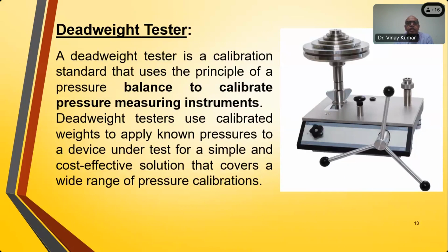The most common and accurate device is the dead weight tester. It is used as a primary standard, and it is a very simple, cost-effective solution covering a wide range of pressure measurement. In this dead weight tester, the main part is the piston and cylinder assembly. There is a piston and a cylinder, and on the cylinder cover we put masses. Hydraulic pressure is used for the high range and pneumatic pressure, air, can be used for the low range.